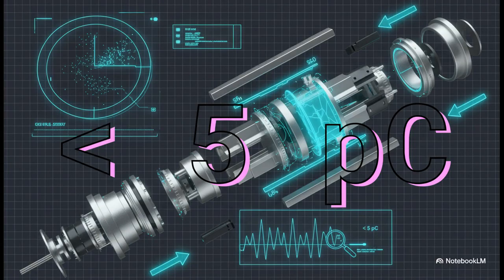Look at this number, less than 5 picocoulombs. That is an unbelievably tiny amount of electrical charge. This is the passing score for what's called a partial discharge test, and it's basically a test for perfection. Any reading higher than this means there's a microscopic flaw somewhere, a tiny speck of dust, a minuscule imperfection that could grow into a massive failure years from now. They are literally listening for an electrical whisper.